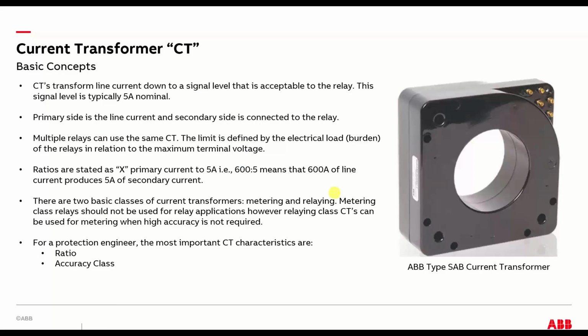The CT is a big part of designing a protective relaying system, because it really sets the size of the circuit you're going to protect. In the medium voltage world, the first circuit breaker frames, there's not as much variation, so you may have a 600 amp, 1200 amp, 3000 amp frame, and that's it. So you set the current for the specific circuit you're trying to protect based on that CT ratio.